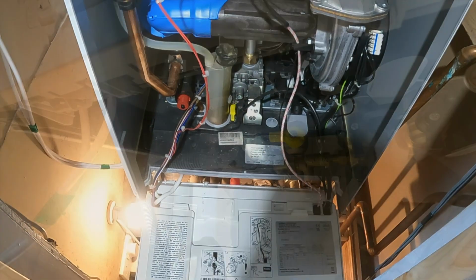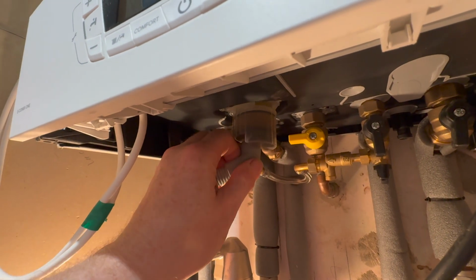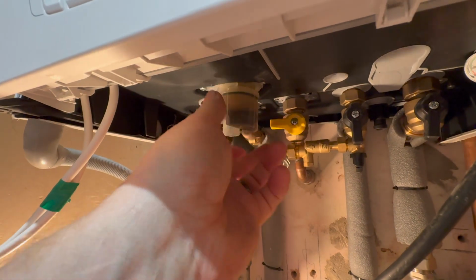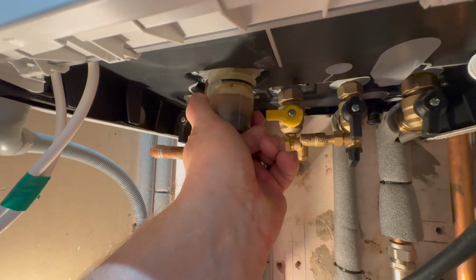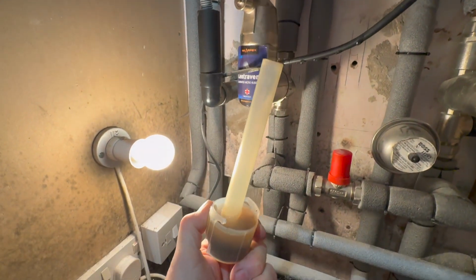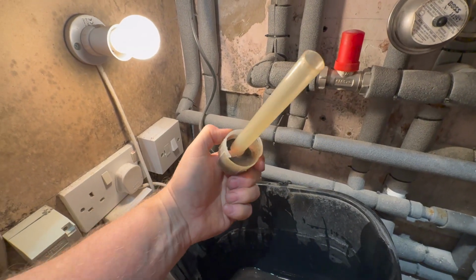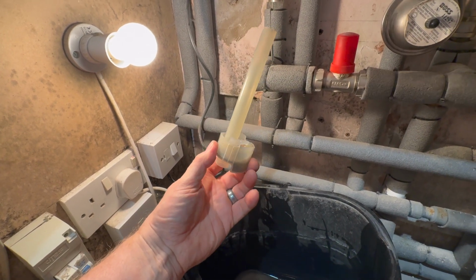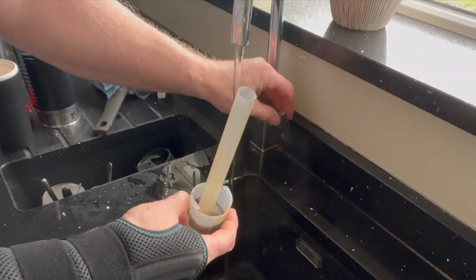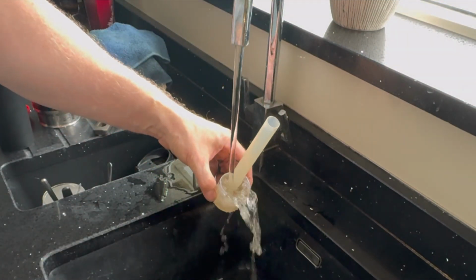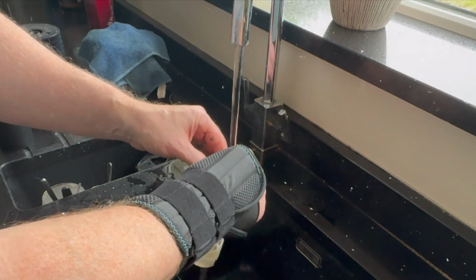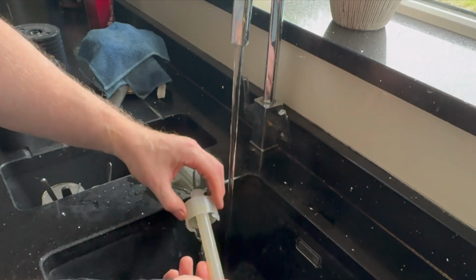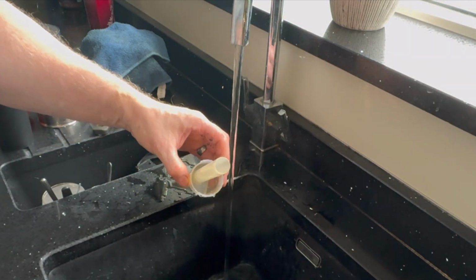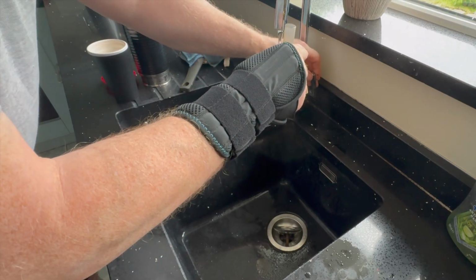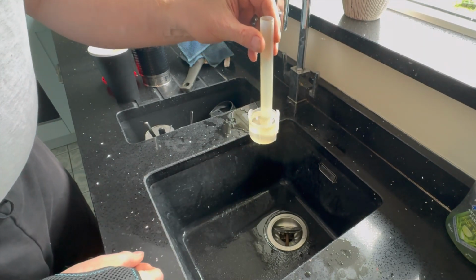There you go, that's back into place. Now it's time to check the trap, so we can remove the flexible pipe off there. And then this is like a bayonet. Now I do have a bucket down at the bottom here to catch the water. So, you can see the crud in there. So yeah, there's quite a bit of crud in the bottom of that. So let's give that a clean out. So let's remove this crud. There you go, nice and clean. Now we will need to fill some water back in here. And now we can put that into the boiler.